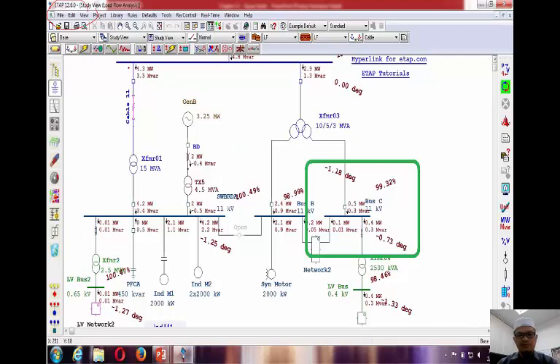This is one of the well-known software. This indicates the bus, and this is the transformer. This is the sending end power, and this is the receiving end power, so from here we can obtain the loss, as well as the voltage shown. For this software, the voltage is shown in terms of per unit or percentage, as well as degree for the angle. So we get real and reactive power, voltage and angle. This is our main purpose of solving the load flow.